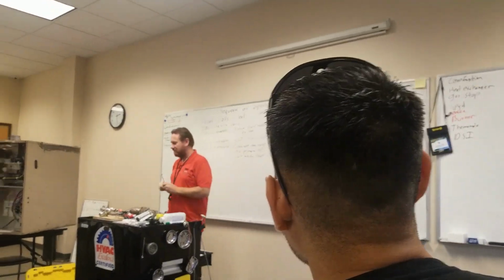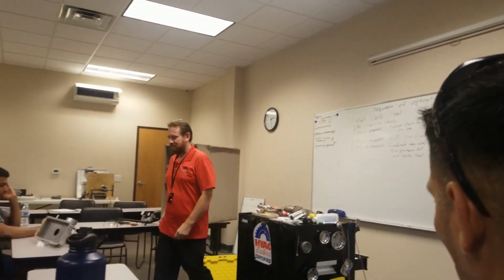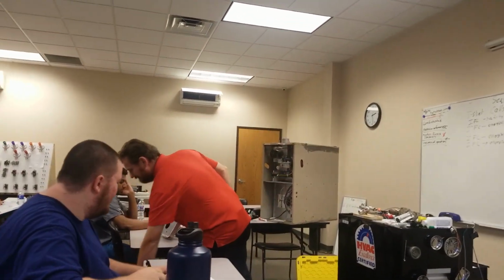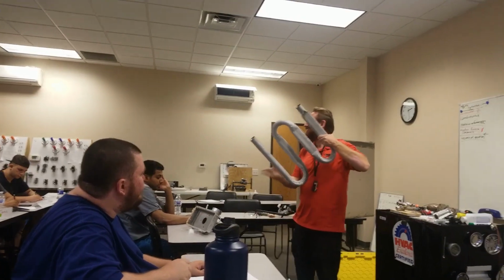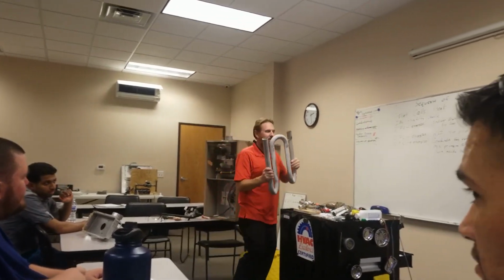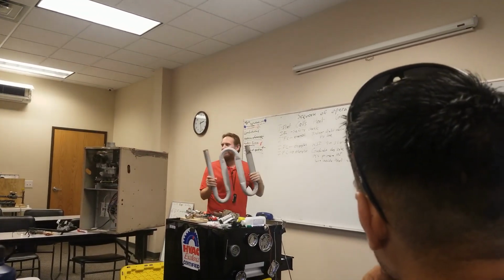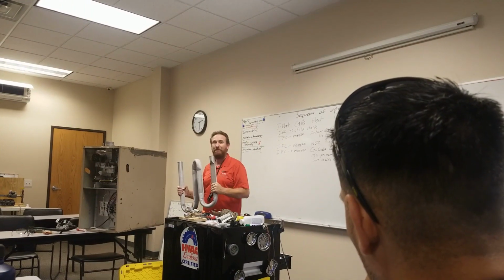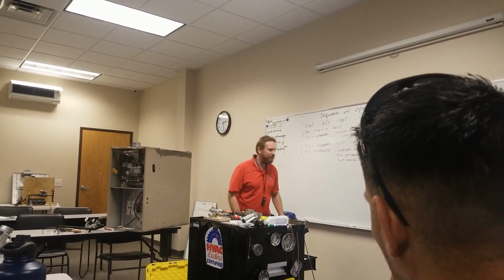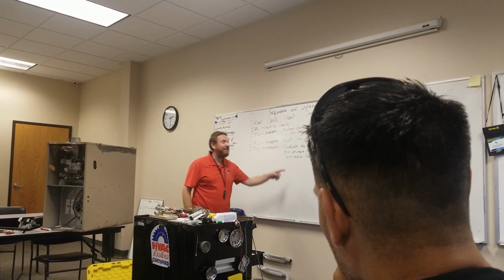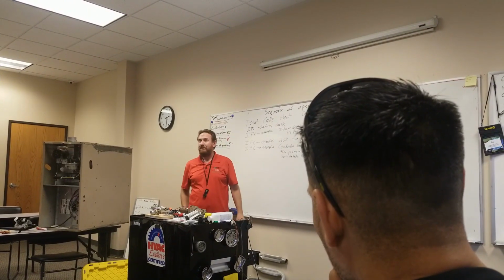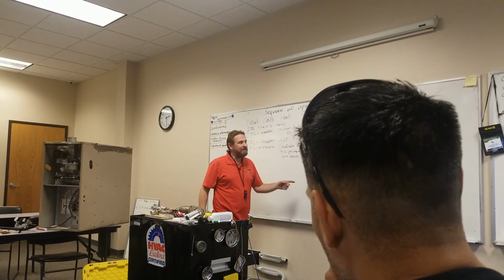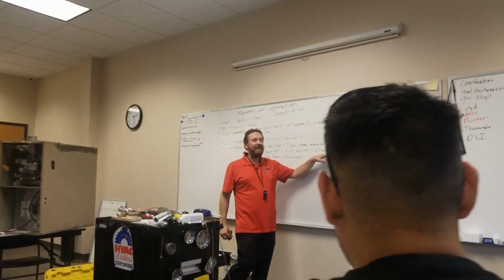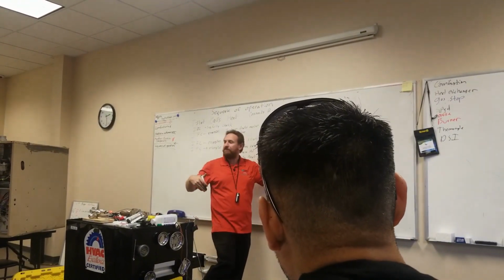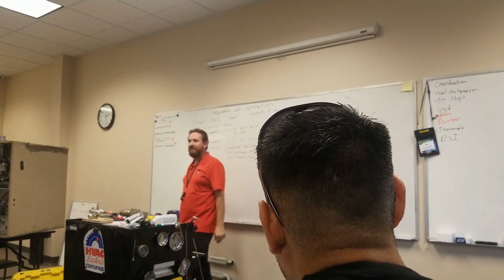Where's the heat exchanger? Right here. The flame's going to burn inside this heat exchanger. That's what's going to happen. If it's not burning inside of this, we have a problem, right? If it's not going across the HSI, is it going to ignite into a flame? Not correctly. I have seen it before where somebody's installed an HSI, but they didn't put it in front of the burners. So it never ignited into a flame.